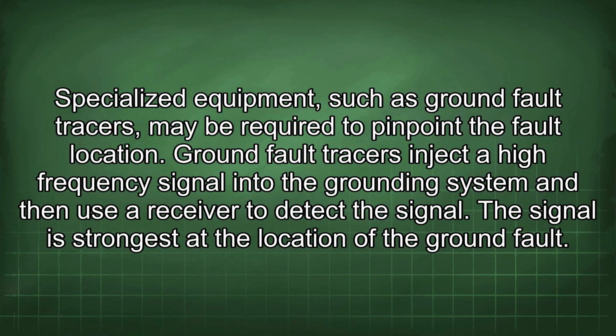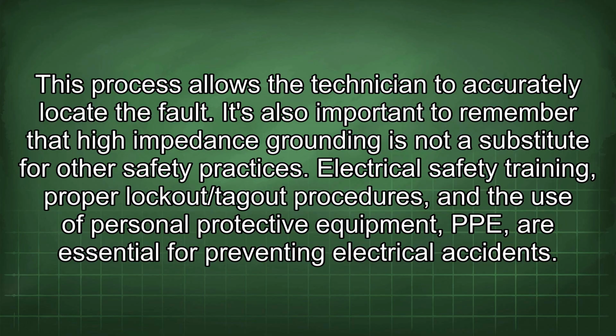Ground fault tracers inject a high-frequency signal into the grounding system and then use a receiver to detect the signal. The signal is strongest at the location of the ground fault. This process allows the technician to accurately locate the fault.